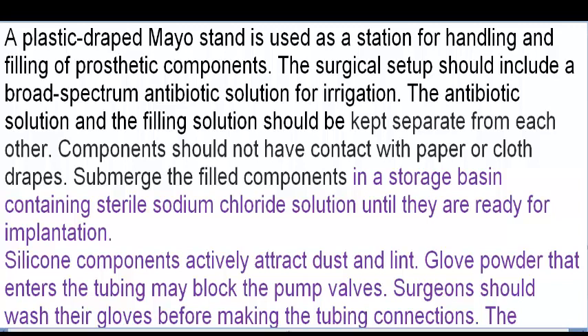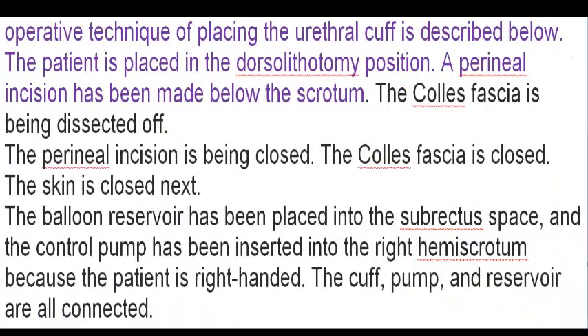Components should not have contact with paper or cloth drapes. Submerge the filled components in a storage basin containing sterile sodium chloride solution until they are ready for implantation. Silicone components actively attract dust and lint. Glove powder that enters the tubing may block the pump valves. Surgeons should wash their gloves before making the tubing connections. The operative technique of placing the urethral cuff is described below.